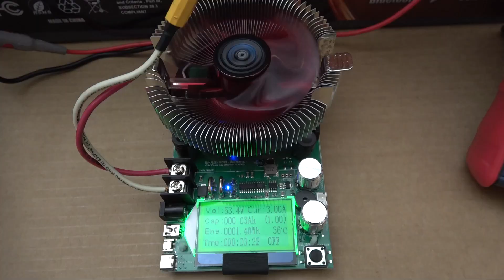Let's go ahead and do a discharge test. We're discharging at 3 amps. This capacity tester can only do about 150 watts, and at 53 volts, 3 amps is about to max it out. This battery is 65 amp hours, so at 3 amps it's going to take about 22 hours.